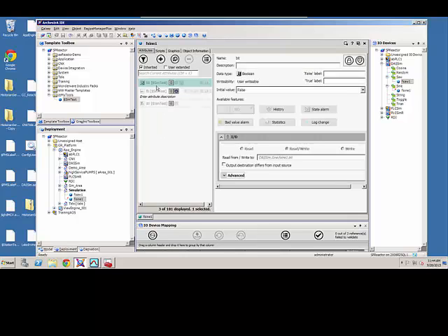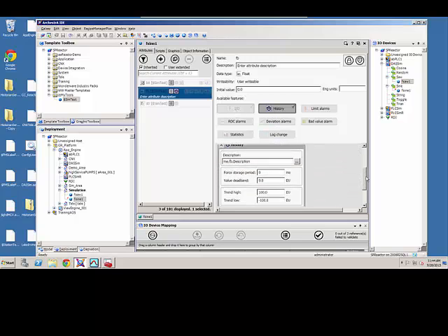If I look at an object that I have here, this thing called sine wave, if I double click on this object, it's got some parameters in here. I'm going to be interested in the feedback bit, .fb. I have I/O assignment checked, and I have history checked, so I want to historize this information. And I'm going to put a trend high and a trend low there so I can see that on my trend when I get to it.